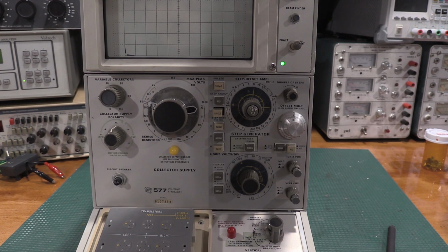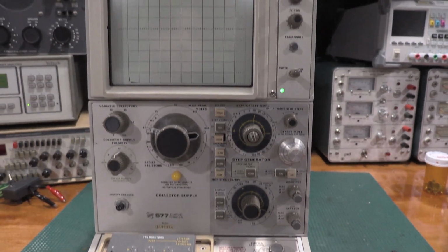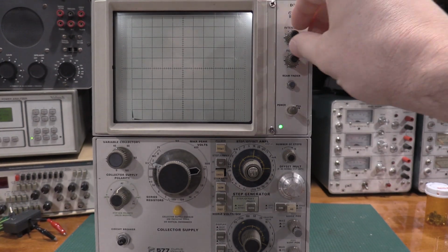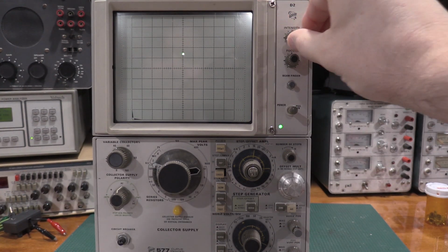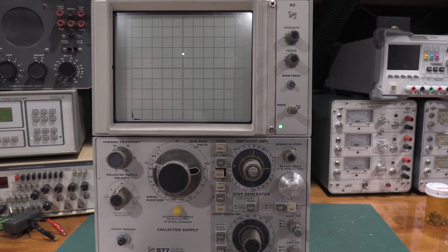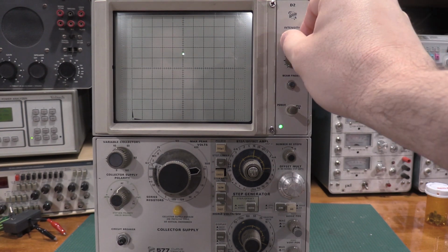So then we turn up the intensity to make sure we can get it, and make sure the focus is off. You don't want a highly focused spot. So we turn up the intensity to make, oh, there's a spot. So we can attain a spot. So that was all we were looking for. Turn the intensity control fully counterclockwise, so completely down.